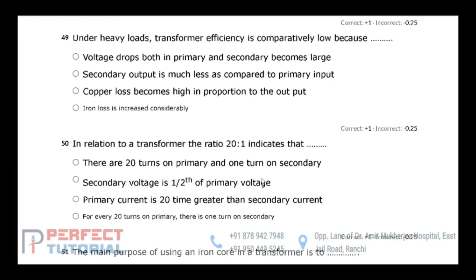See, under heavy load condition, copper loss becomes high and that is proportional to the loading, and this causes the lowering of efficiency. So simply copper loss would become high, which is proportional to what? Which is proportional to the output, or which is proportional to loading.